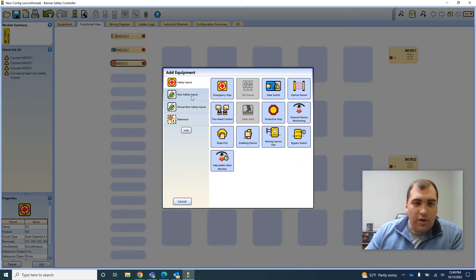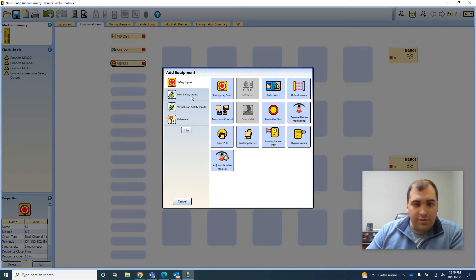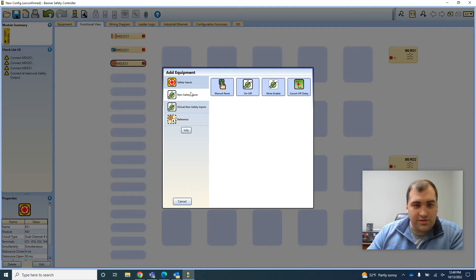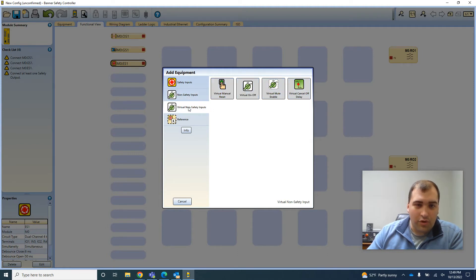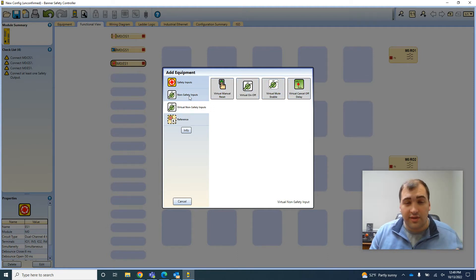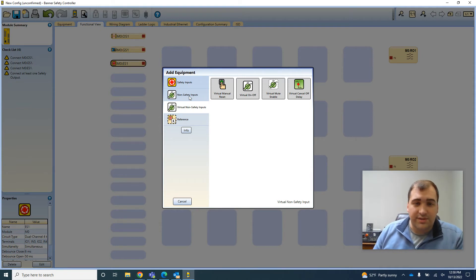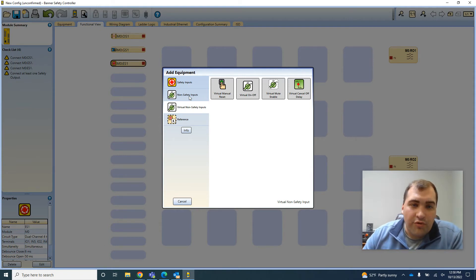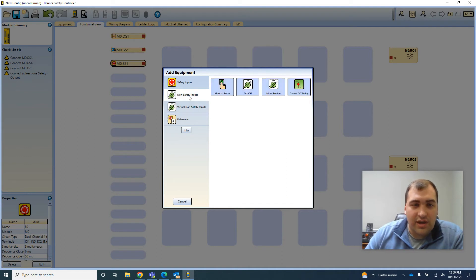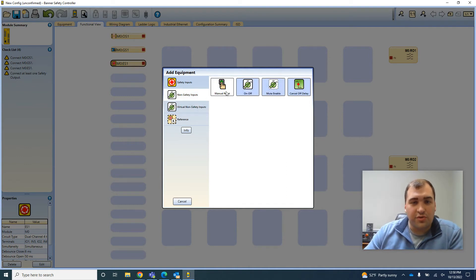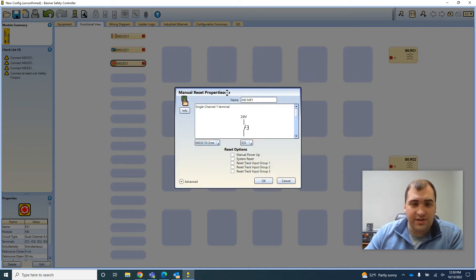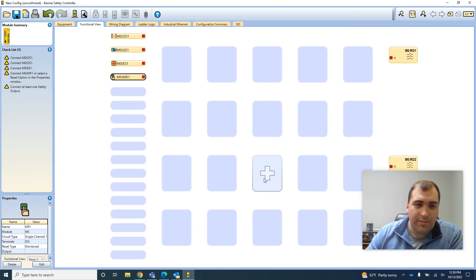And then when I want to reset, I'm going to want a non-safety input. You can choose those either as a physical or you could do a virtual, because you can connect out using Ethernet connection, Modbus TCP IP, Profinet as options to communicate. I'm just going to do a physical wired manual reset button.